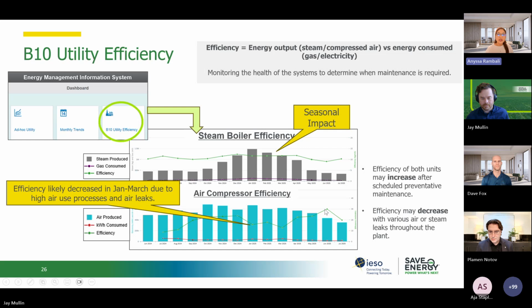So for the steam boiler, there's a seasonal impact as our plant uses steam for heating and also for our process. I would say the efficiency of both units may increase after scheduled maintenance, so that's something to observe. A decrease in efficiency would indicate, for the air compressor, maybe leaks throughout the plant.